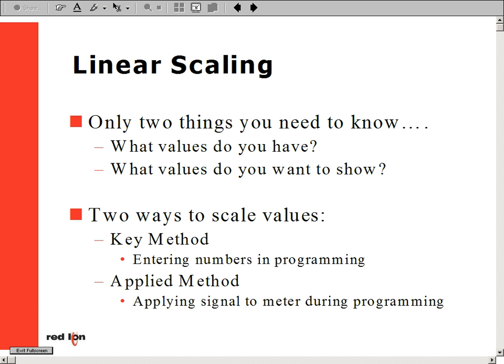Our example shows us having a flow sensor giving off a 4 to 20 milliamp process signal. Our meter then, in turn, needs to be scaled to read 0 to 100% on the display. The following steps will show us how to plug in the proper parameters to successfully scale this meter.